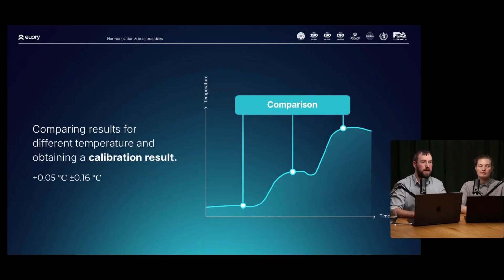But the second part is just as important, the uncertainty. So how precise is this comparison? So in this example, it will be plus minus 0.16 degrees. And what does that mean? That means that with 95% certainty, the result will lay somewhere between plus 0.21 degrees and minus 0.11 degrees.